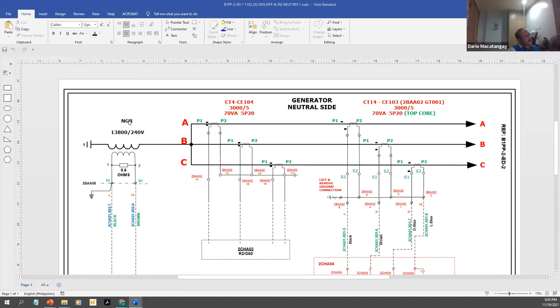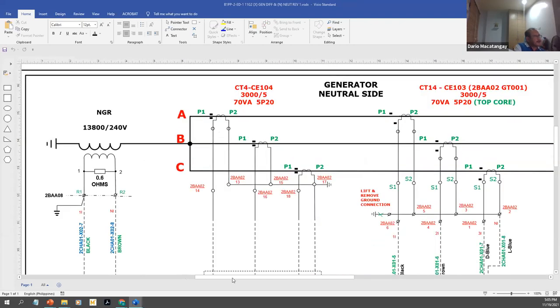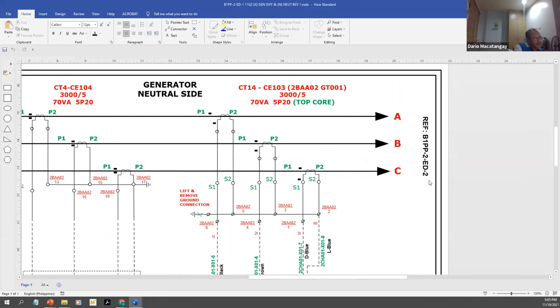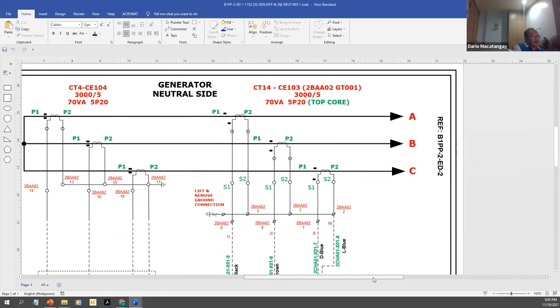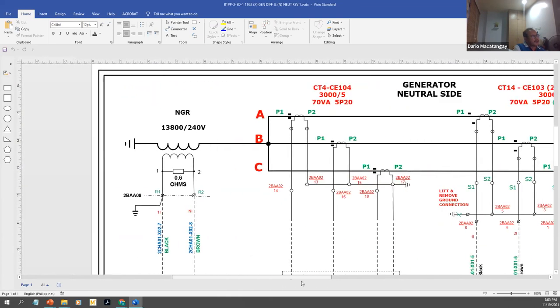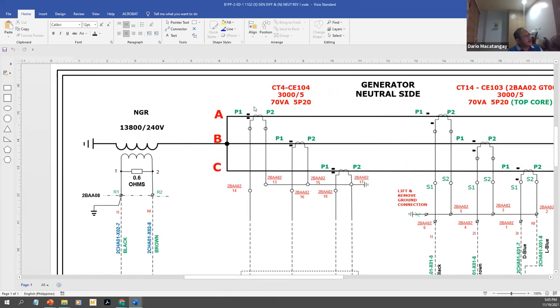And you can see here, these are your CTs, okay? These are the CT. This is your power circuit here. This is your neutral. This is the neutral connection here. And this actually goes to other portions of the circuit. This is just part of the whole system, a very small part of the system. So during normal condition, current will flow here, right? On the A, B, and C. These are high voltage, so you need to reduce the current and the voltage to a smaller value for relaying purposes, okay?